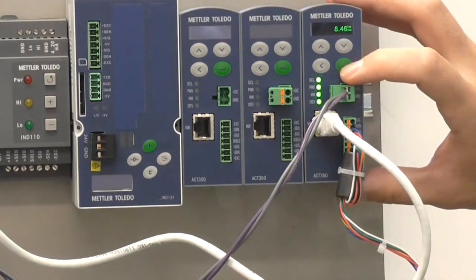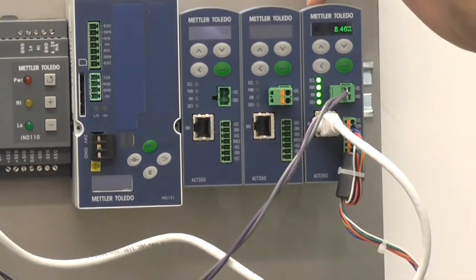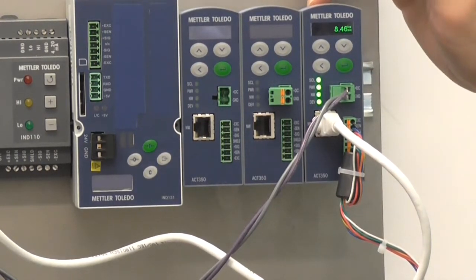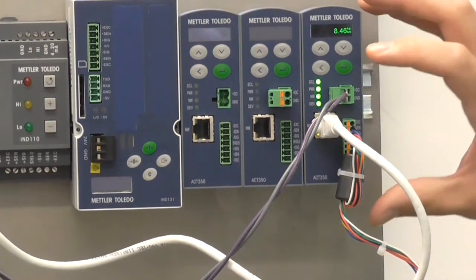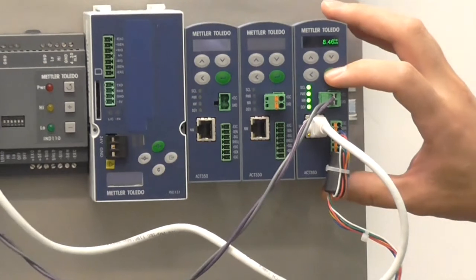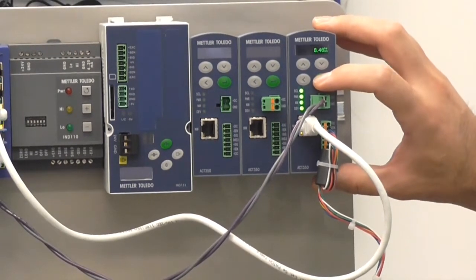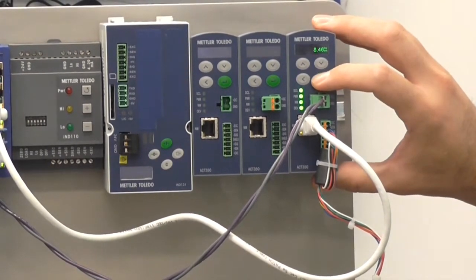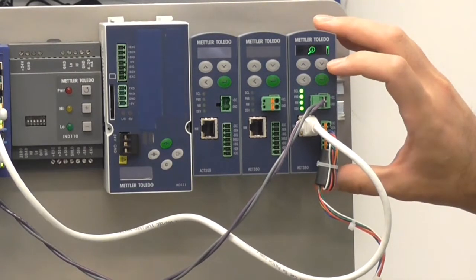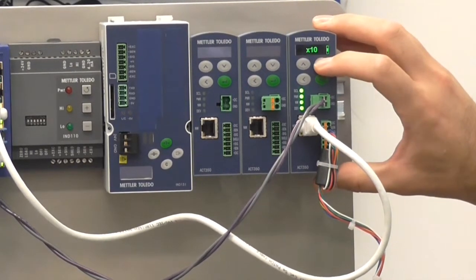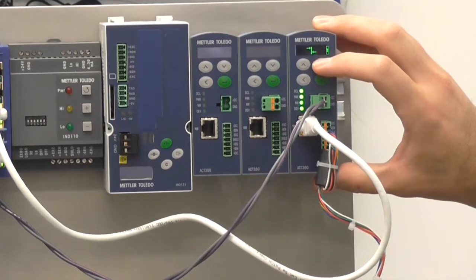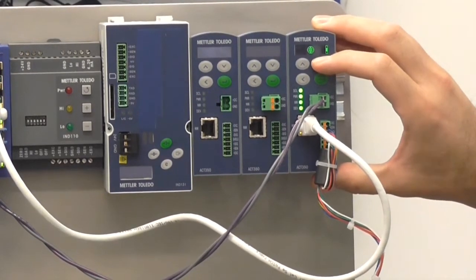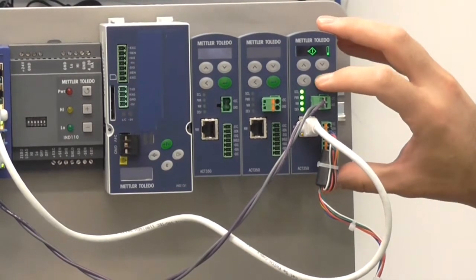For how to get into the configuration, you can either configure using your laptop using software called Setup Plus, which is available free on our website. But for the purposes of today's demo, we're going to program using the front keypad.